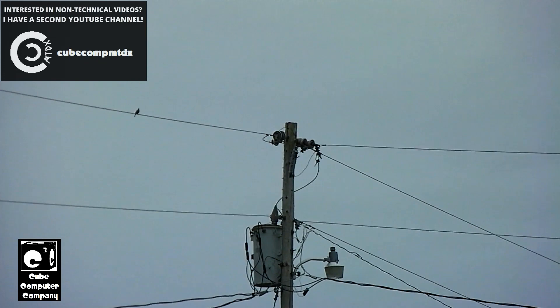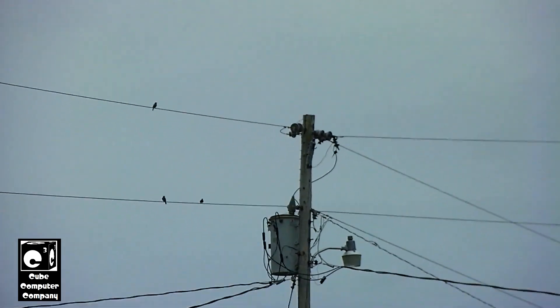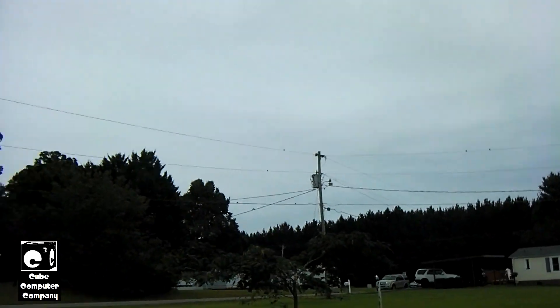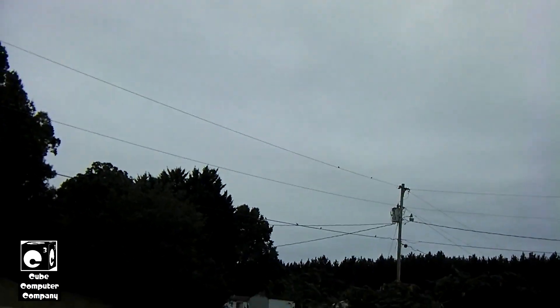Out there is a transformer on the pole, and that's the one I was showing in the previous video. I made the video because a few days earlier we had a power outage in this neighborhood where this sideline lost power due to overgrown trees and vines getting into the line, and it popped this fuse at the top of the pole. It's called a fuse cutout, and the fuse link is inside a barrel that gets loaded into the cutout.